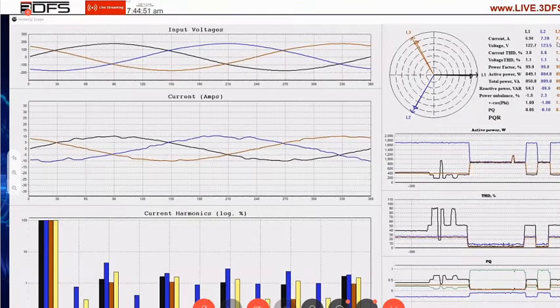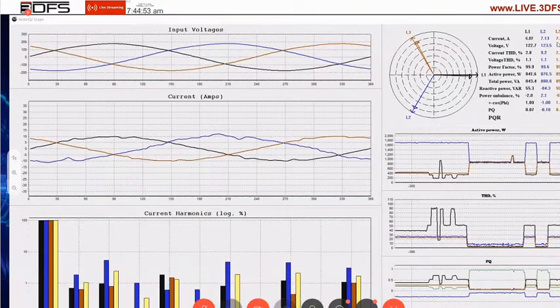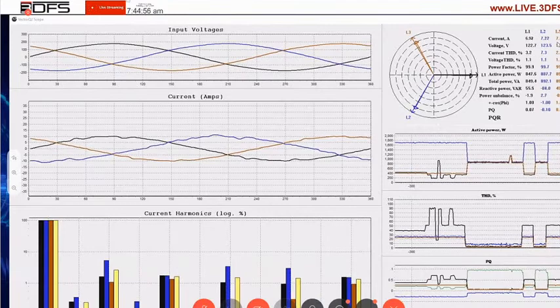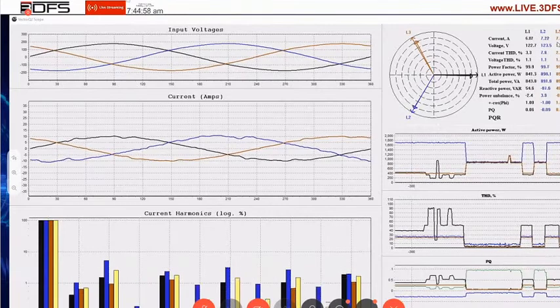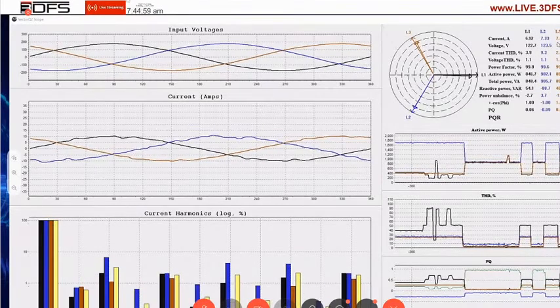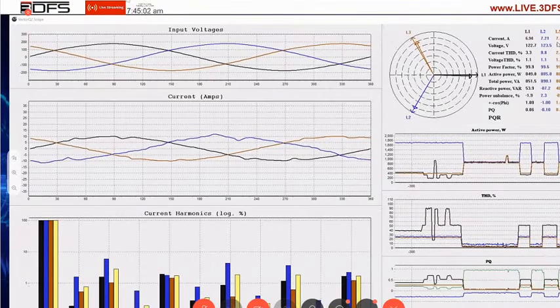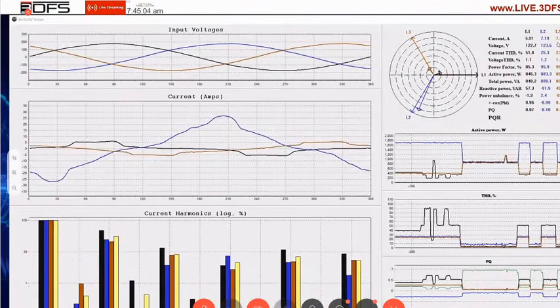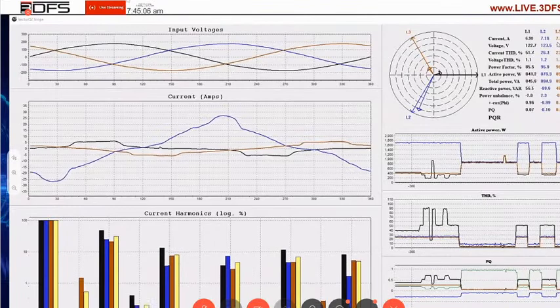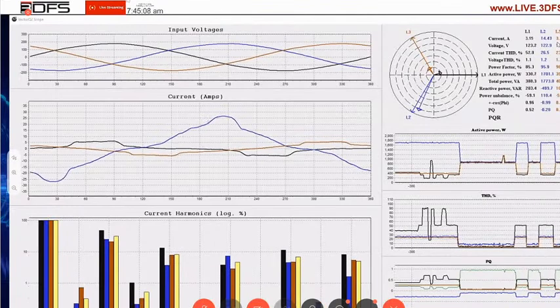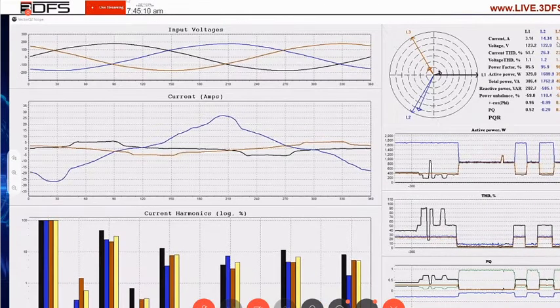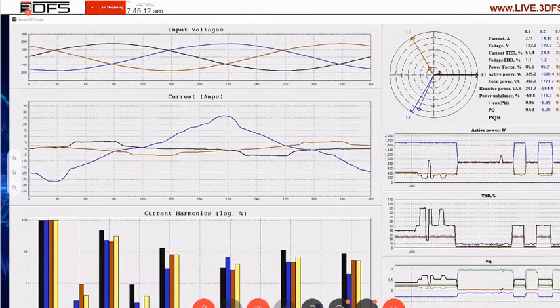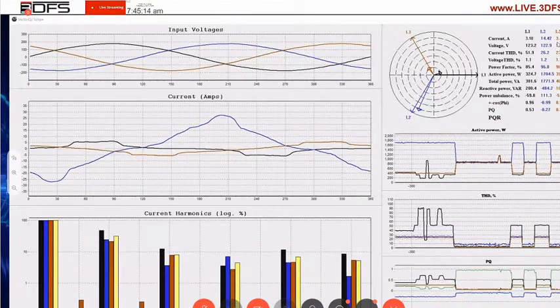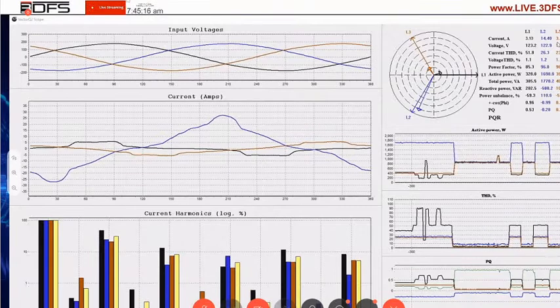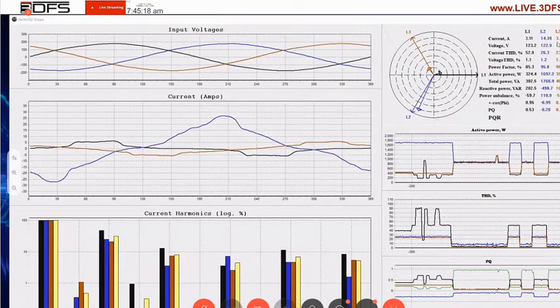That function is what is mainly missing today—that real-time phase balancing, in addition to some of the other stuff. But that's a huge advantage on power distribution. When there is no imbalance in the network, it significantly reduces power quality issues. As I mentioned, the eddy currents in the upstream transformer that exist will go away—all of a sudden it's no longer there because of the balance.